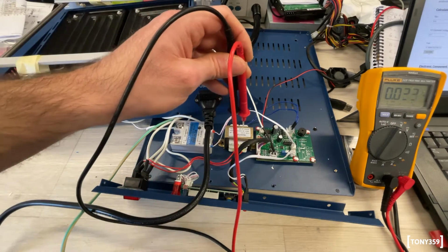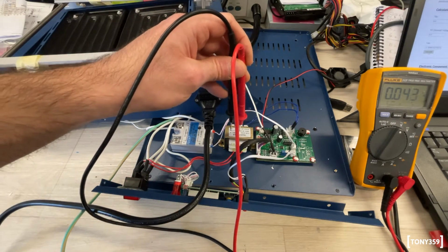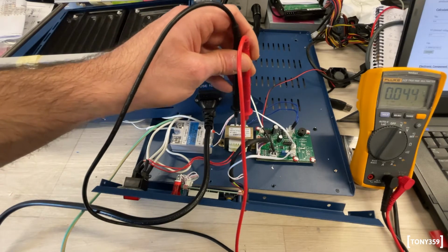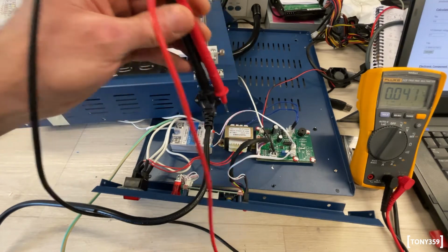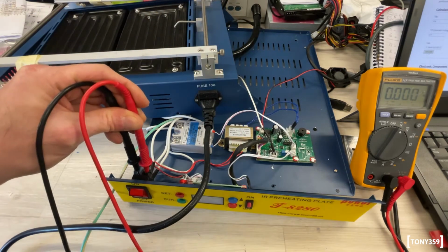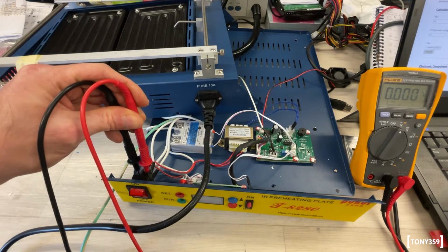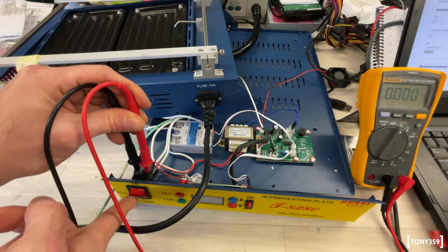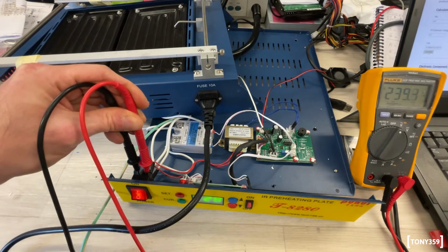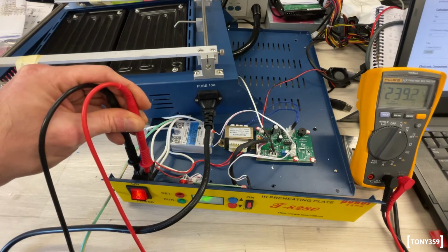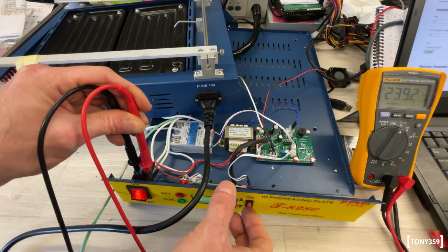I'm just concerned that I may want to replace the power supply and the problem is still there, because it's not the power supply dropping, but it's actually the 240 dropping a little bit. So I'm now connected to the main switch after the switch. If I power up, I read 239.3, which is my mains voltage here. And let's see what happens when I power the plates.